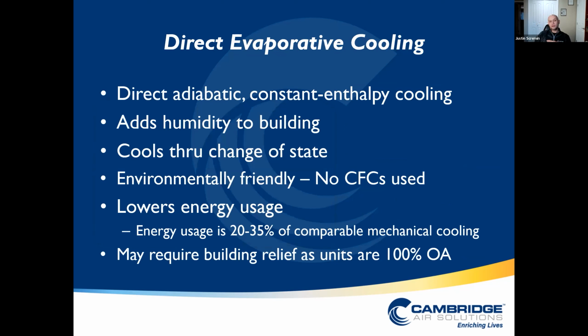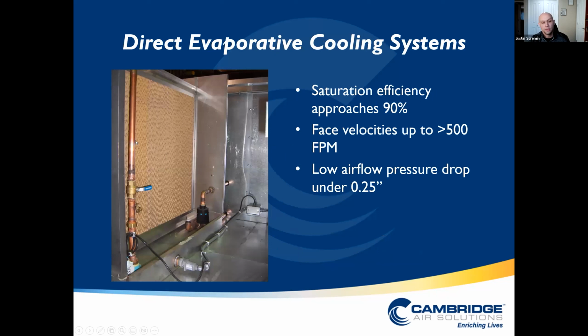So why would we use a direct evaporative cooler? Well, we would typically use one in a building where we do not care about how much humidity is in the space. The drawback of a direct evaporative cooling piece of equipment is it is mixing air and water. It's very similar to a cooling tower. We are drawing water down a piece of fill and we are blowing air across it. So the air and the water are in direct contact with each other. We saturate that fill and we blow air across it. And so all of the humidity, all of that latent energy that we've added to the air gets carried into the building. And so for that reason, we have to be cautious on how we control that.